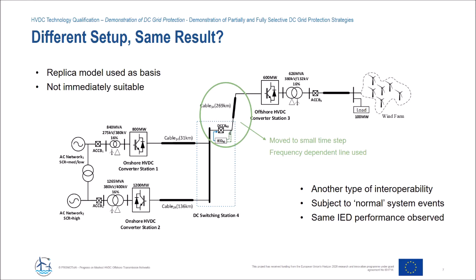So in summary for this bit, we've demonstrated successfully the operation of fully and partially selective protection schemes on the most realistic test case we could do without actually putting it on a real system. The key takeaway is that the IED's performance is expected to be sufficient for potential future HVDC grids. Through this, we evaluated the interoperability, looking at multi-vendor protection systems, and we've developed real-time models that can be used for benchmarking performance of real IED devices using hardware-in-the-loop testing.